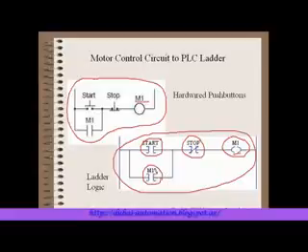Now, actually, I don't like to do this. This is not where we like to stop. We like to take this relay coil, take a contact that would come back from that relay coil, and then enter that into our PLC program. And therefore, we have a real-world understanding when we seal our circuit in. If this relay were to drop out for any reason in the field, then it would also drop our seal in the program.